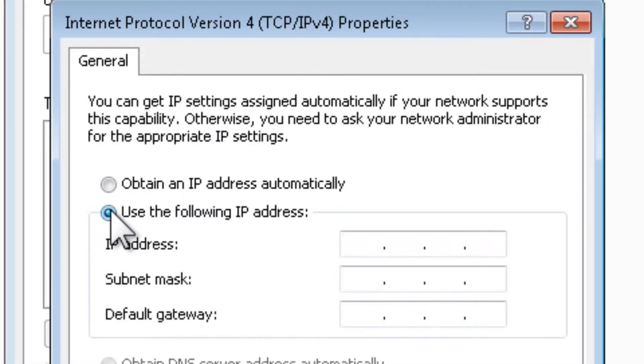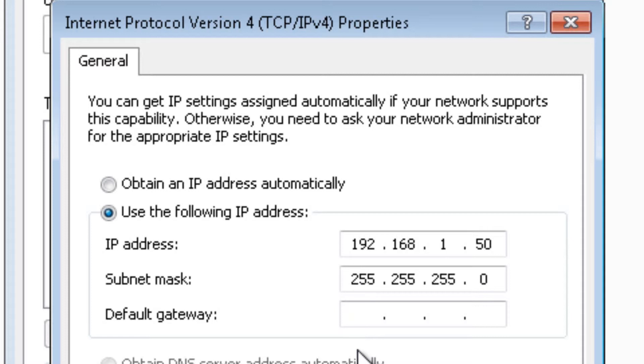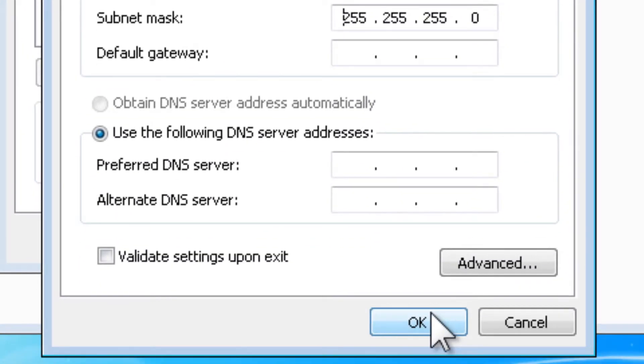Change to Use the following IP address. The PC must have a different address than the controller. If the MPIEC controller is 192.168.1.1 by default, then the PC can be, for example, 192.168.1.50. The subnet mask will autofill with 255.255.255.0. Click OK for the setting to take effect.